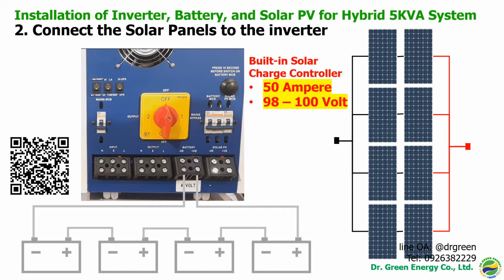Every time you install, you need to check the specification or data sheet of your particular solar panel to determine what the voltage will be for each string when in series, and when paralleling, the total current of all strings must not exceed 50 amperes.